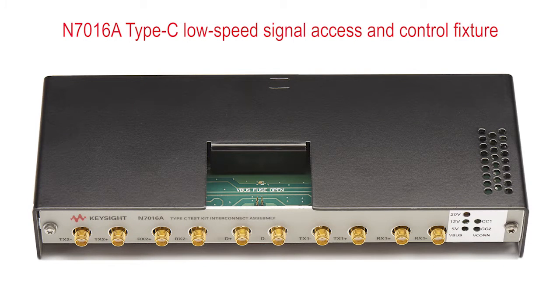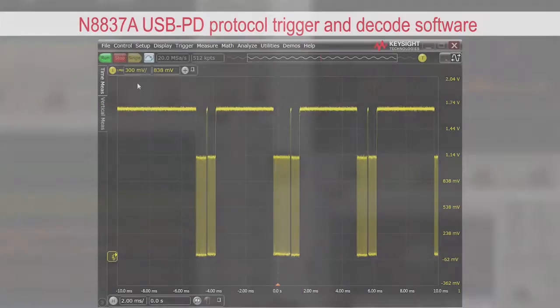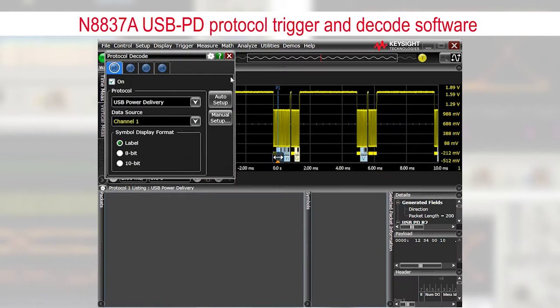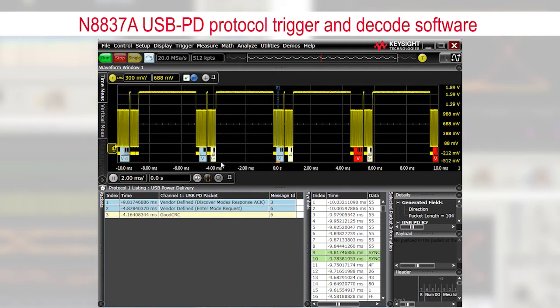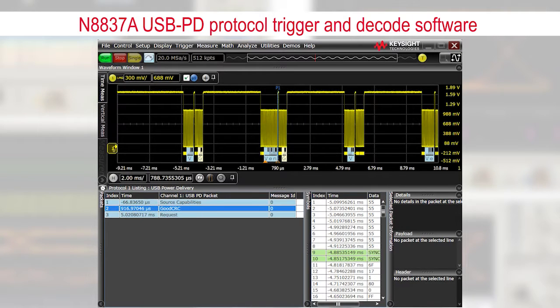The first part of testing USB PD is debugging. This fixture is specifically designed to help you debug and test the 300 kHz CC line and VBus lines for USB PD. We have also designed a specific power delivery probe to allow you to very accurately characterize your VBus signal. We have a new USB PD protocol trigger and decode software that allows you real-time triggering of the USB PD CC line.